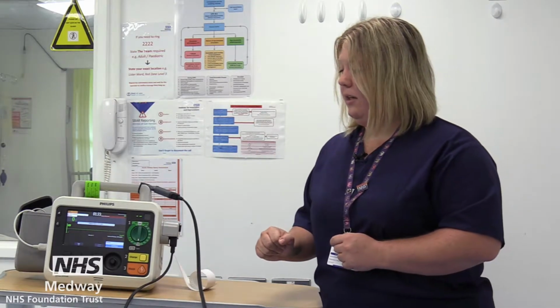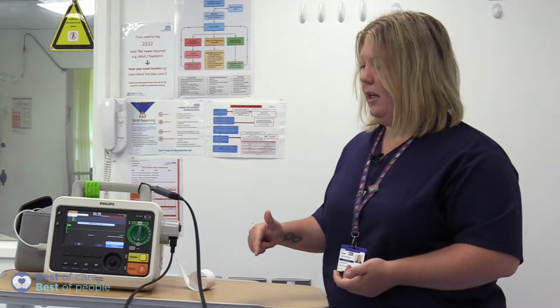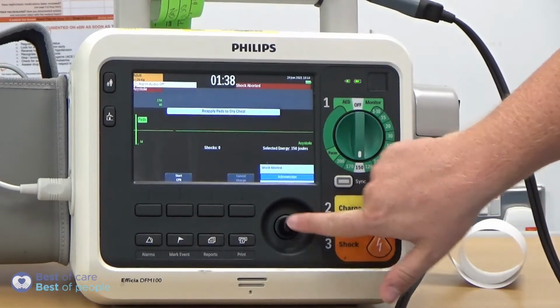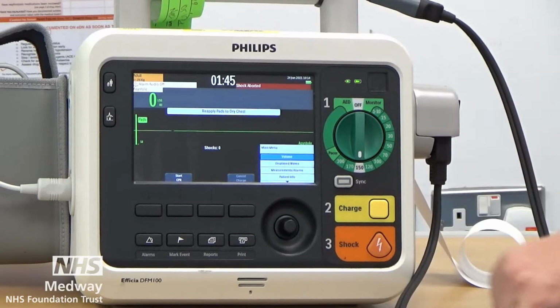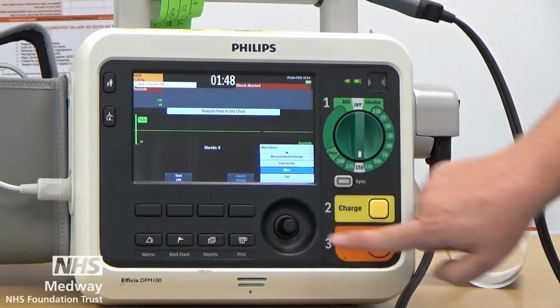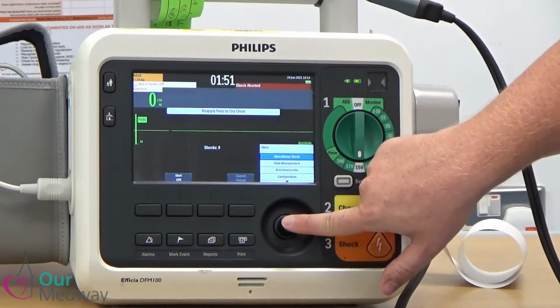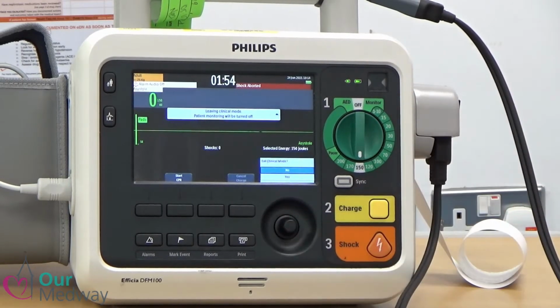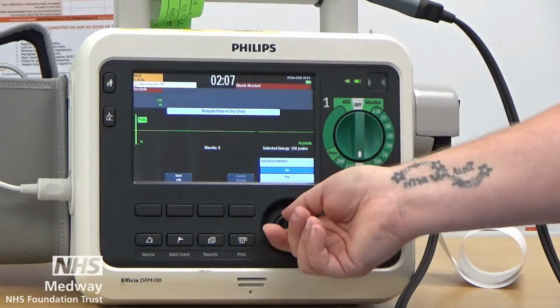So the next one I'd like to show you is how to do an operational check. So this operational check is the one we would like you to do once per month. And it's a more in-depth check looking at all of the leads and all of the functions within the defibrillator. So if we just get rid of the acknowledgements. So to do the operational check, we hit the menu button. We dial down to where it says Other. And then operational check, run operational check, and it will ask you, are you sure? It's asking you, are you sure? Because you will be leaving clinical mode. So whilst you're doing an operational check, this defib will not be functional on a patient, and that's why it asks that question. So we'll say yes.